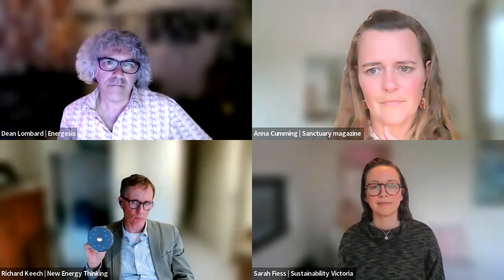So all other things being equal, if you halve the use of hot water, then you halve the size of the tank you need. So I guess I differ a little from Dean there in that I'm comfortable recommending people have fairly small hot water tanks, so long as they've chosen the shower head very carefully. If they've decided they can live with something like this, and believe me, I think it's not a compromise at all, then you can use quite a small tank. Like the house we've just built, we have a 160 litre tank. It's a Reclaim Energy heat pump hot water service, with these shower heads, and we had 5 people there over Easter, and we didn't run out.